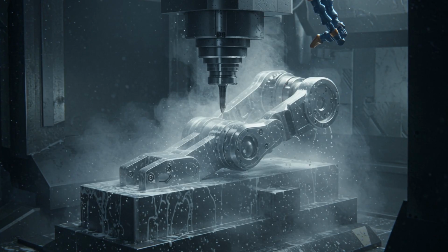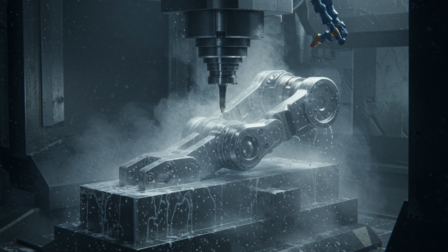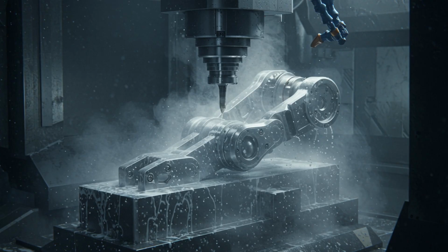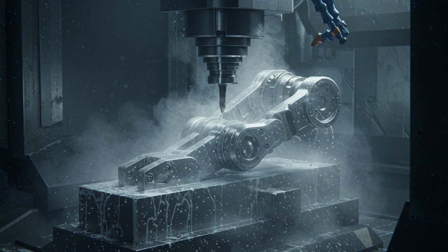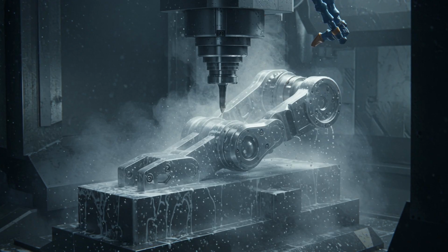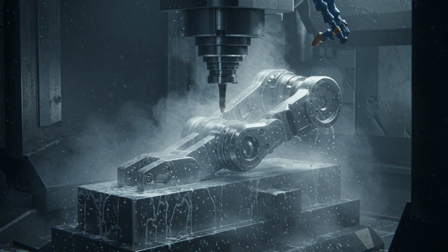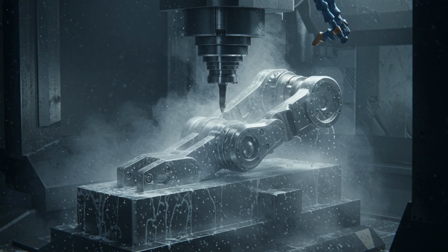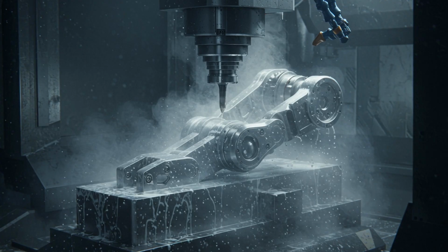Following the machining, the components undergo a multi-stage cleaning process to remove any microscopic burrs or industrial oils. They are then treated with a specialized medical-grade coating, often a matte finish, to prevent glare from intense operating room lights. These limbs must be capable of a range of motion that exceeds the human wrist, meaning the joints must be designed with complex internal channels for wiring and cabling, all while maintaining structural integrity. Every gram of weight saved or added is calculated to ensure the motors can respond with zero latency and absolute stability.